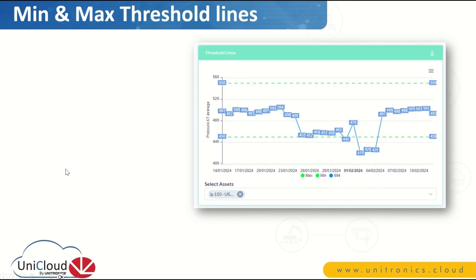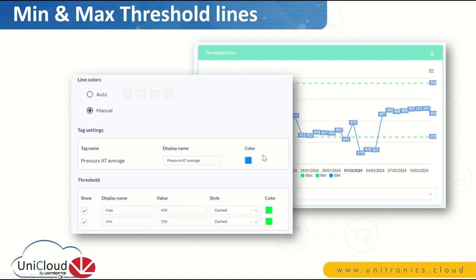With the new version, we are introducing a new type of KPI tool: minimum and maximum threshold lines. You can see an example on screen. These threshold lines are at the widget level — they are not cross-platform, because they are related to a specific parameter, in this case pressure. For a specific system pressure, you can place a minimum and a maximum. You can define the name, the min, the max, the type of line, and the color. You can decide to show both, one, or none of them. It's very straightforward and easy to use. However, it is still at the widget level, not cross-platform, because the min and max are related to a specific pressure parameter.